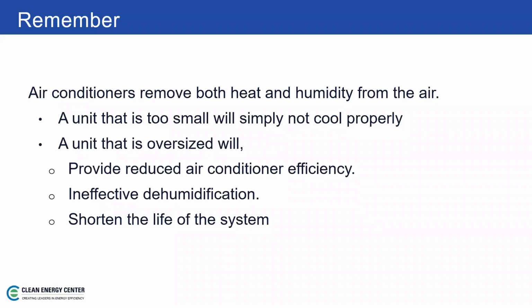So if a unit is oversized, it will end up short cycling. And if that happens, you're going to have reduced efficiency. It's going to cost them more to run their air conditioner. The dehumidification process isn't going to work very well at all, so they might have a cool room, but it's going to be a clammy feeling. The more you oversize, the more that impacts the dehumidification. And because it short cycles, it'll end up shortening the life of the system, which we don't want. And if it's too small, it's simply not going to cool properly.